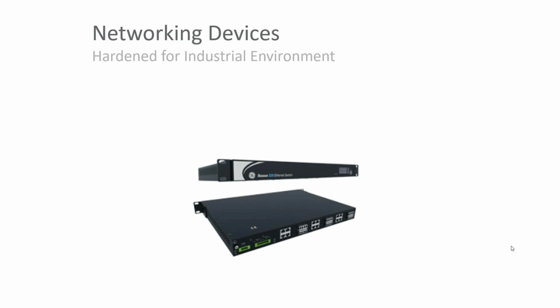Just a little bit on this, not a plug or commercial thing with the slide, but make sure your devices, your switches, your routers, know what they need to know. If you're designing for an industrial utility application, we're familiar with relays, which are substation hardened and must meet certain EMC and IEC standards. Make sure your switches also meet those standards. You're not going to go to Best Buy and get a switch and expect it to work in a substation environment. You need industrial hardened switches that meet all the normal standards a relay meets.